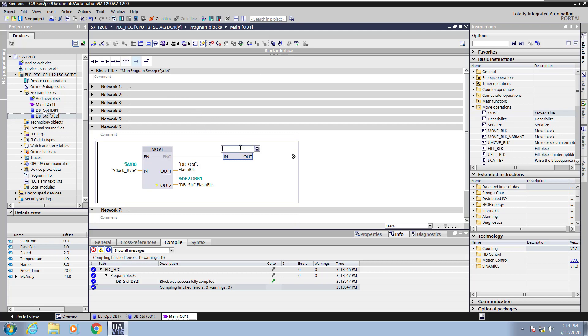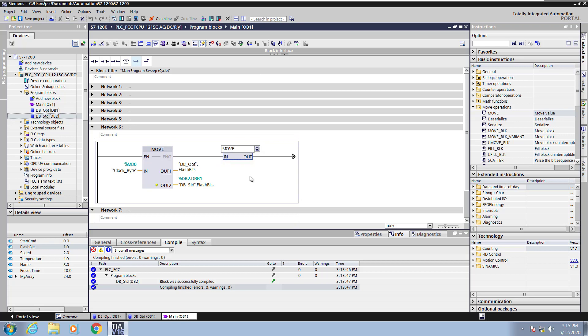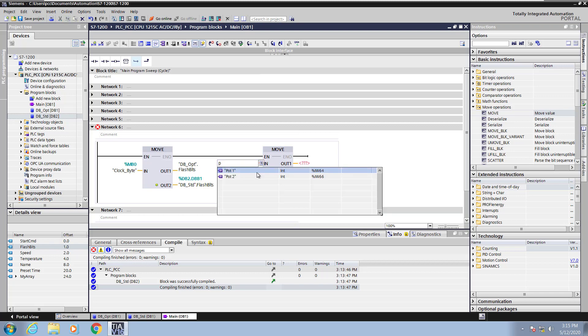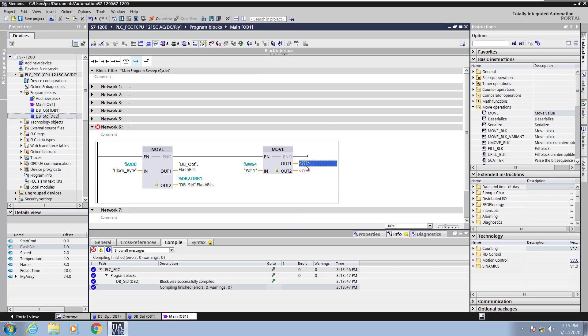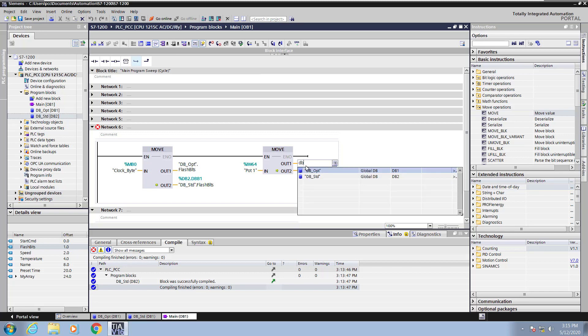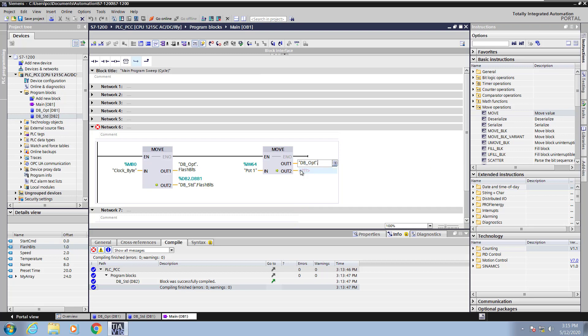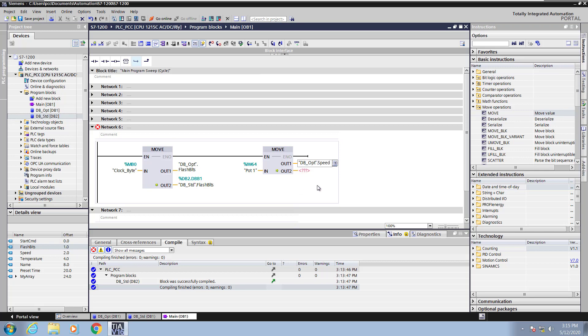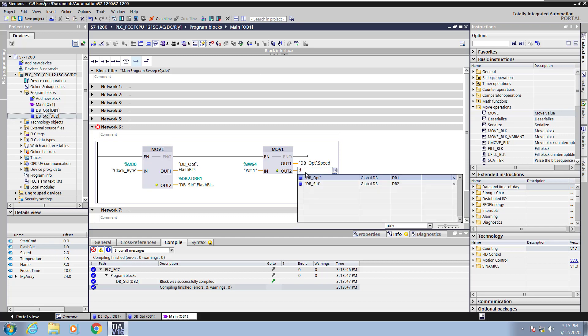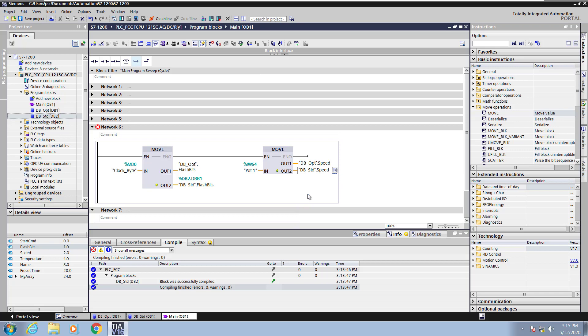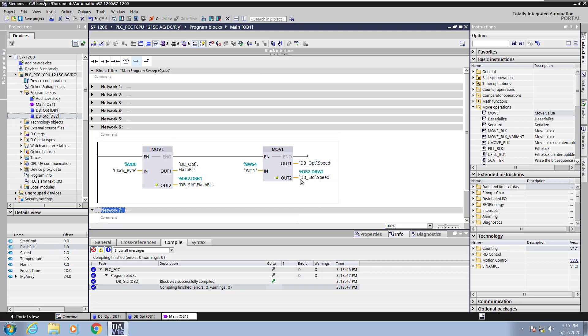I will add in another move instruction. I'm going to use an empty box instruction and just type in the instruction that I'm looking for. So I'm going to use the move. This time I will add in another additional pin but on the input side I'm going to use the analog pot value. So I'm going to select pot one and now instead of doing the drag and drop method I will just start typing the first few letters of a data block. So I'll use my optimized access and then I'll drill into the data block to pick the speed tag. I will do the same thing for the standard access. So now I'll start typing the first few letters of the data block. Select my data block and then drill in and select the speed tag. So with the standard access you have an absolute address as well as name address and an optimized access you just use names only.